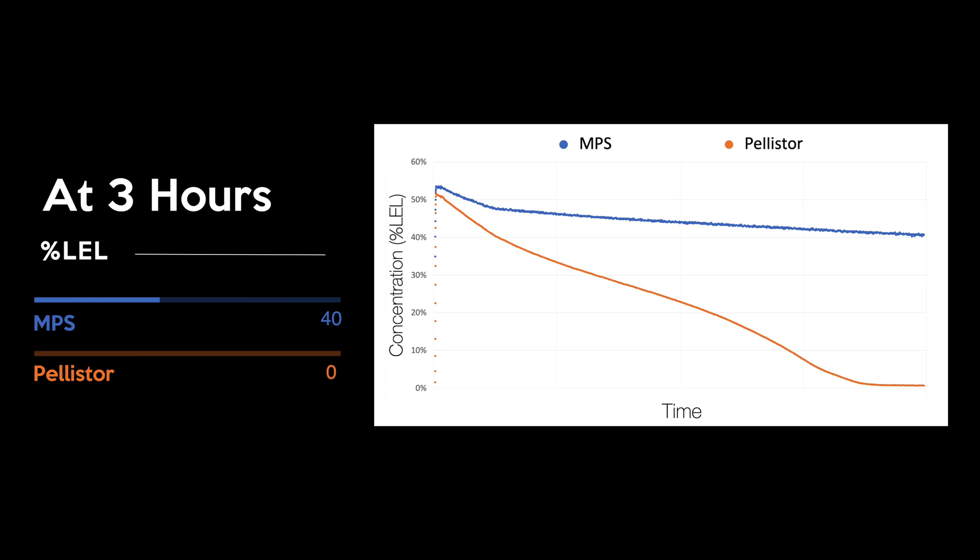Now I'll remove the lid to remove the poison. Both sensors have returned to reading 0% LEL now that they are back in clean air.